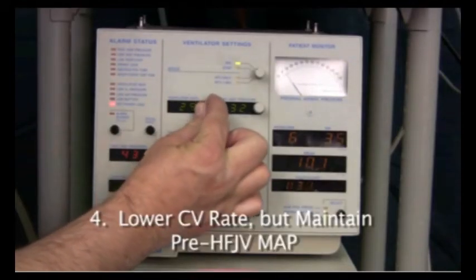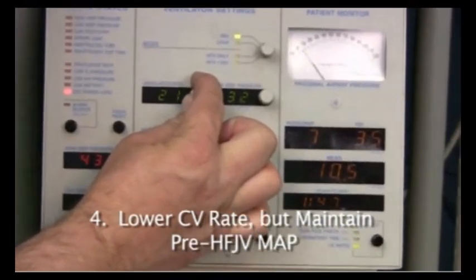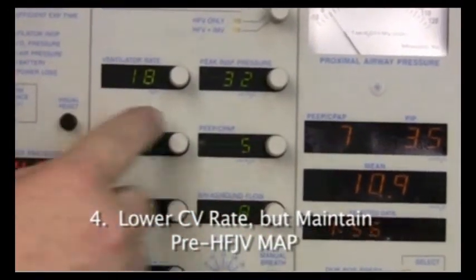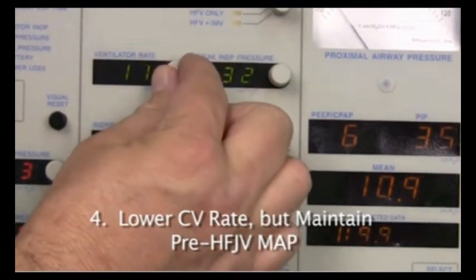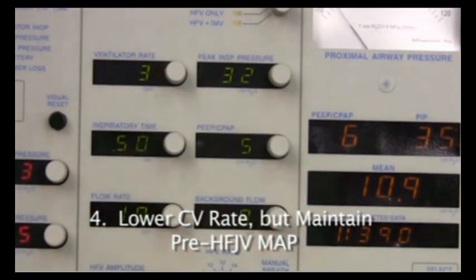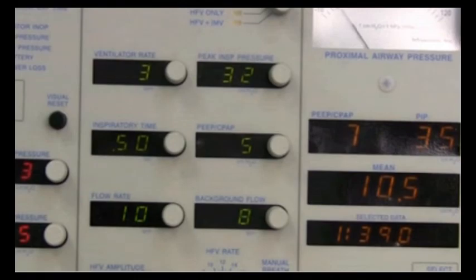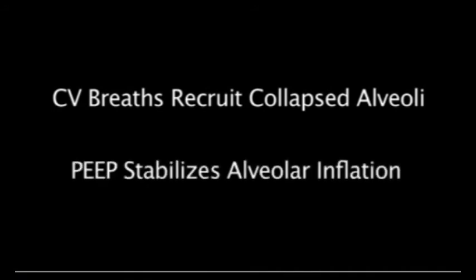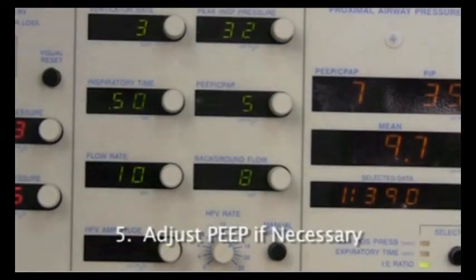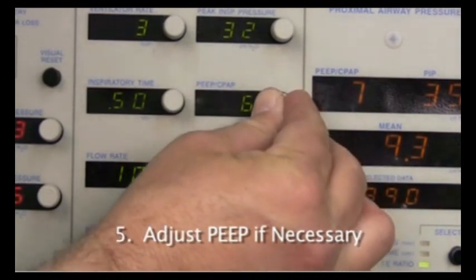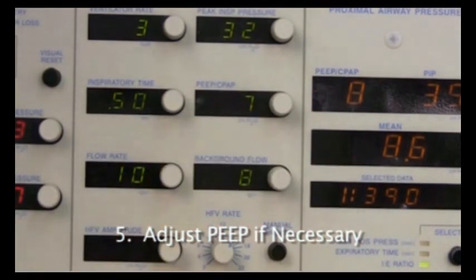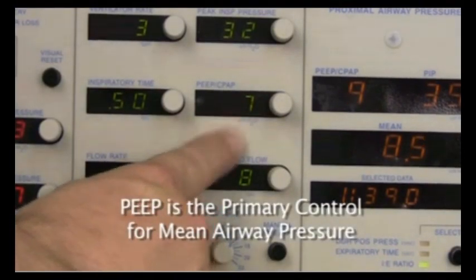Fourth, lower the conventional ventilator rate down to about 3 breaths per minute, making sure to maintain your pre-high-frequency jet ventilation mean airway pressure. If necessary, provide 3, maybe up to 5 breaths for non-compliant lungs until your optimal PEEP has been reached. So the sigh breaths serve to open the alveoli. The PEEP serves to keep the alveoli open. Fifth, adjust the PEEP or the CPAP setting as indicated to optimize mean airway pressure and to maintain adequate oxygenation at the lowest possible FiO2.